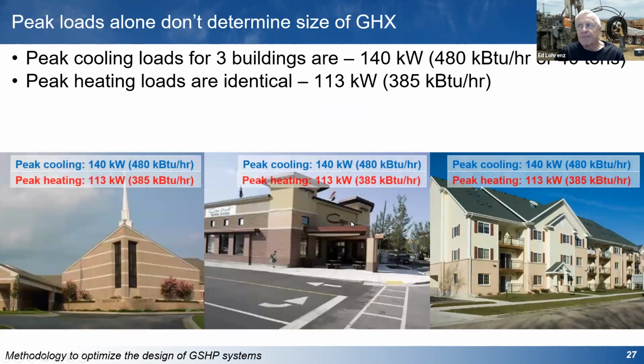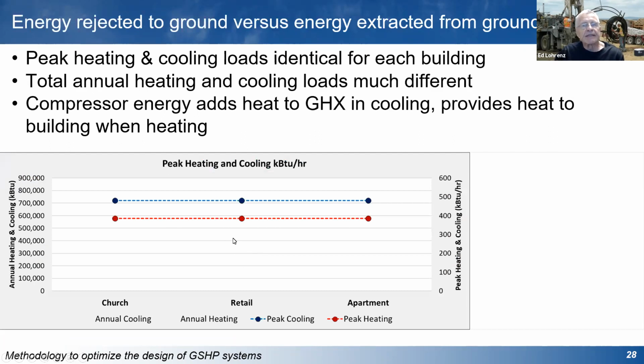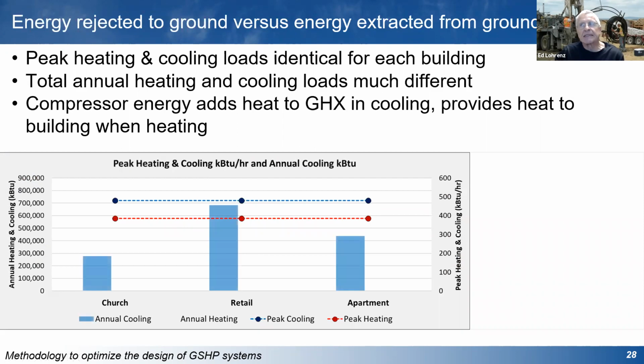But to really demonstrate the problem with using only peak loads to estimate the size of a ground heat exchanger, take three buildings: a church, for example, a retail store, and an apartment building. Assume the peak heating and cooling loads are identical, roughly 40 tons in cooling, 480,000 BTUs per hour, and heating loads of about 385,000 BTUs per hour. If we design the ground heat exchanger based on that, we're only designing on the peak loads. We're ignoring one of the fundamental things that an energy storage system needs to be aware of. A church, for example, is going to be cooled for a few hours a week. A retail store is going to be cooled for a lot more hours, so it's going to be dumping a lot more energy.